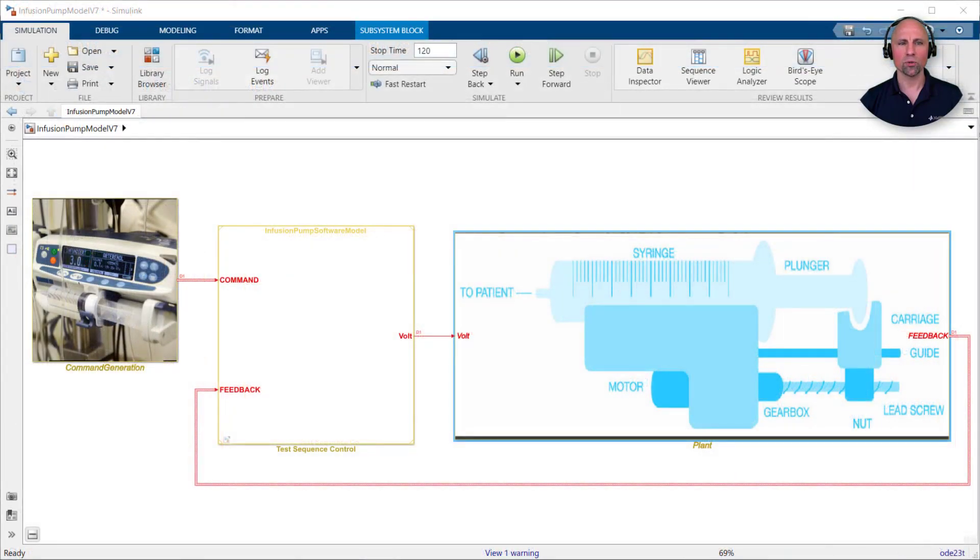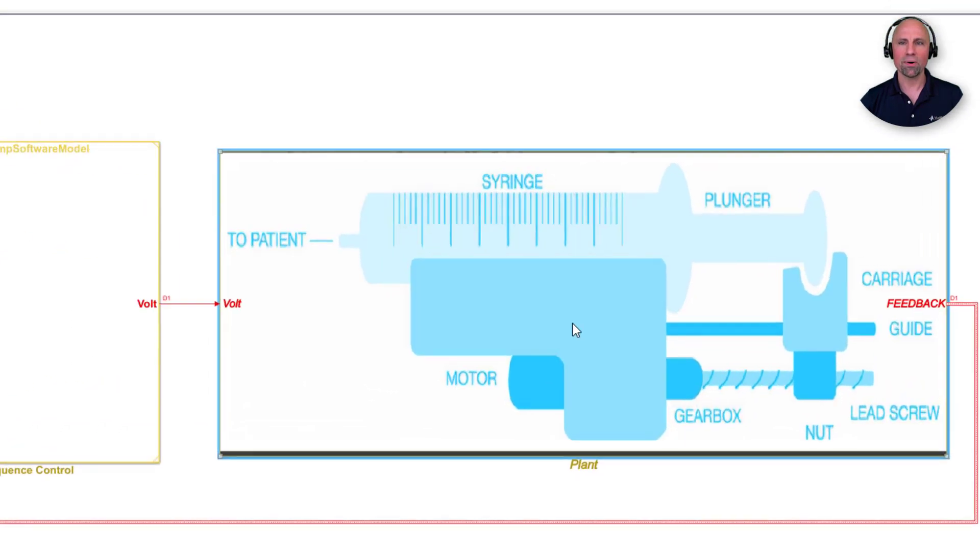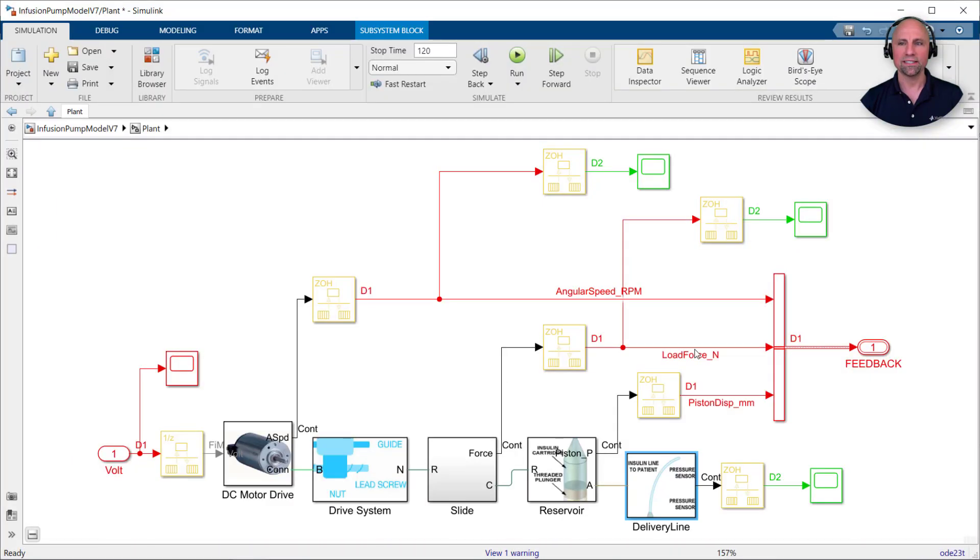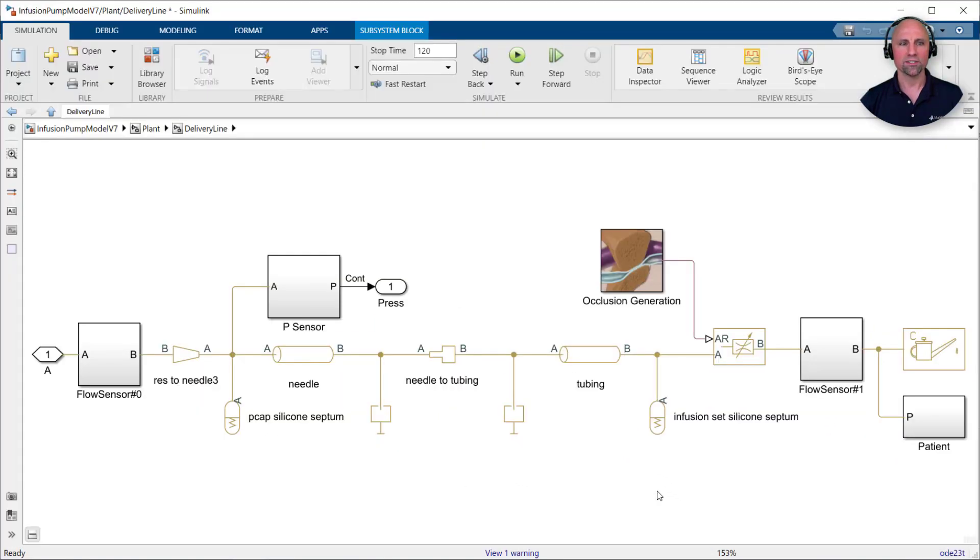At this top level we see interconnected blocks modeling a user's interaction with the embedded software and physical components of the device. Clicking into the plant model we see a DC motor and drive system have been implemented to depress the plunger. Opening the delivery line block we see the tubing and flow sensor are being modeled with Simscape components.